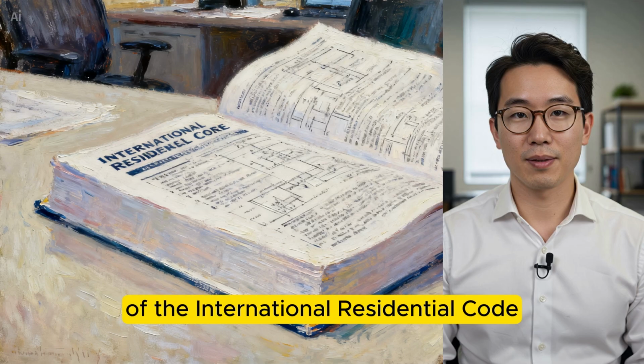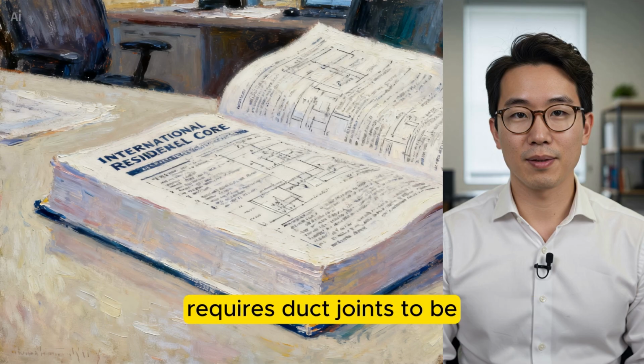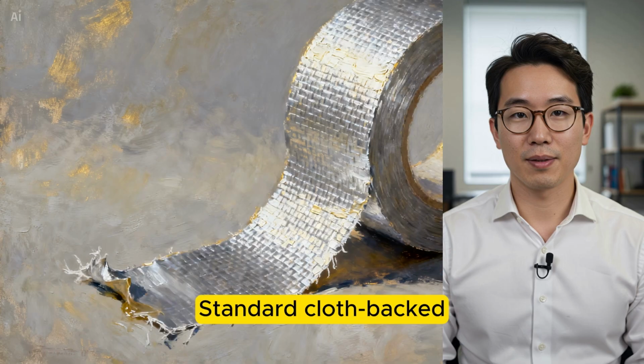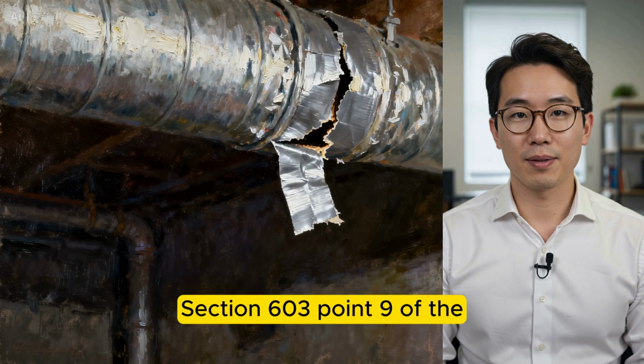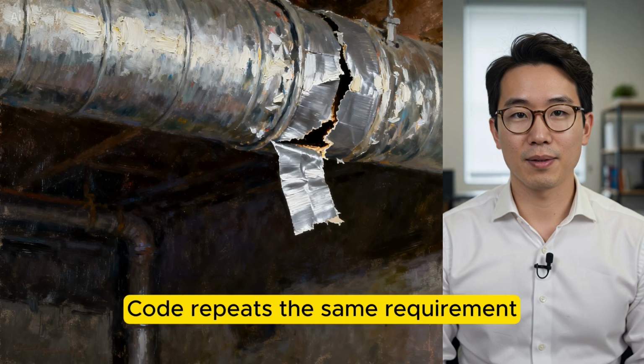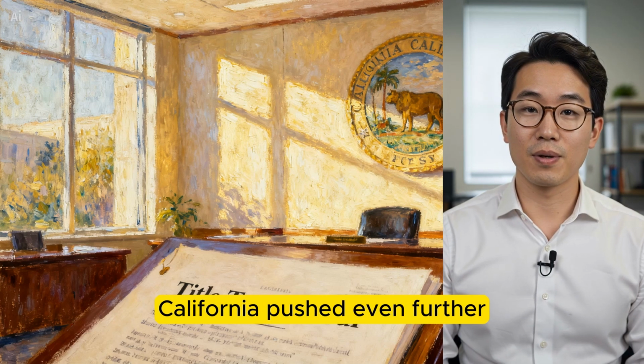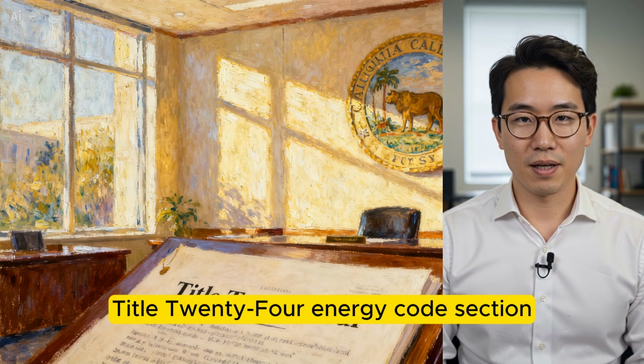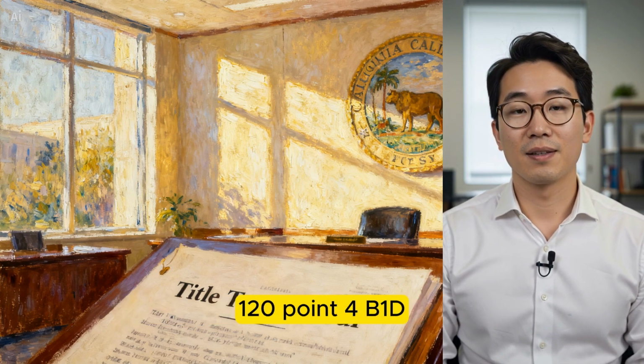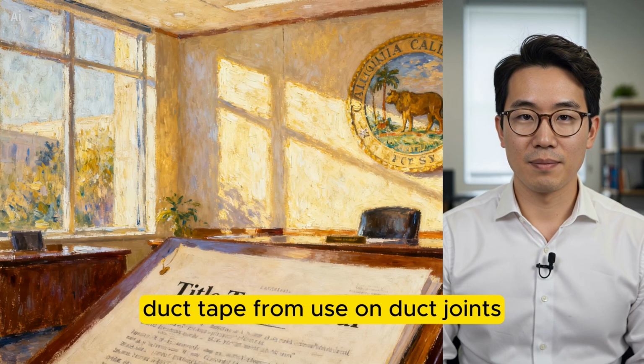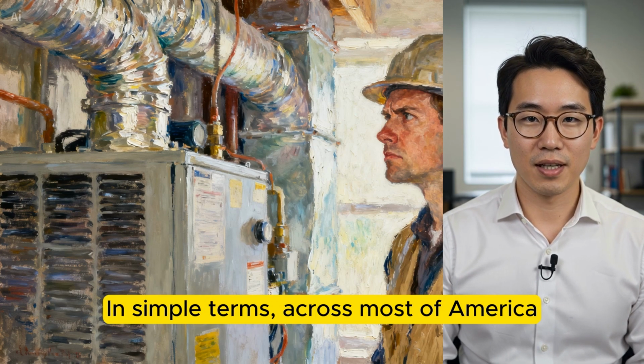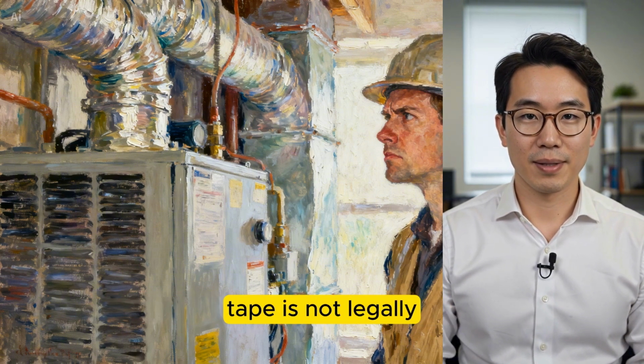Section M1601.4.1 of the International Residential Code, the model standard used by most states, requires duct joints to be sealed using materials approved under UL 181A or UL 181B specifications. Standard cloth-backed rubber adhesive duct tape qualifies for neither category. It fails both tests. Section 603.9 of the International Mechanical Code repeats the same requirement. California pushed even further. Title 24, Energy Code Section 120.4 B1D specifically bans cloth-backed rubber adhesive duct tape from use on duct joints.